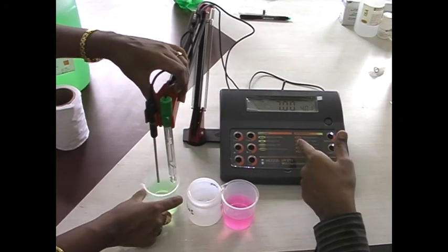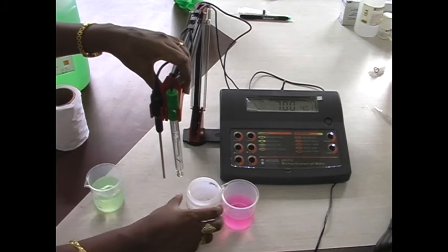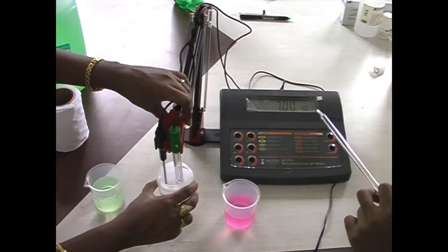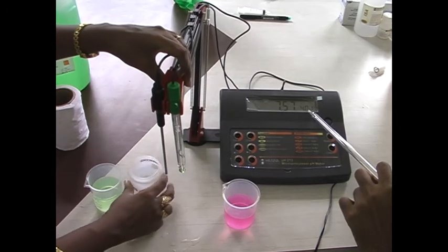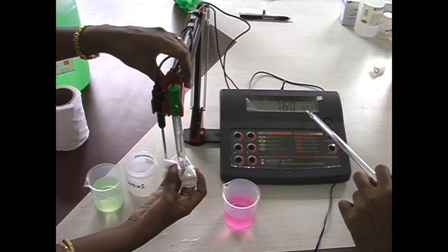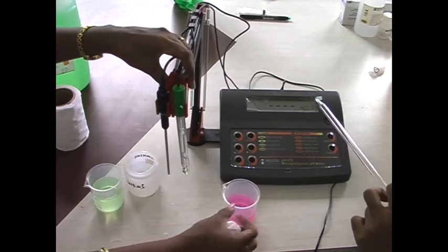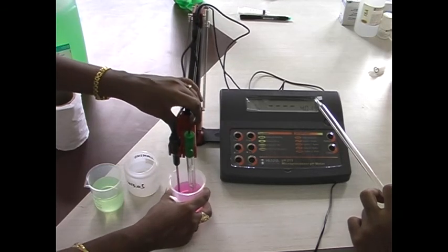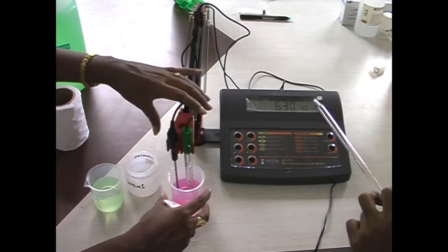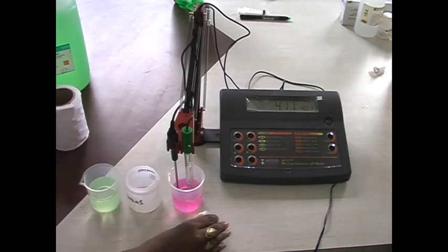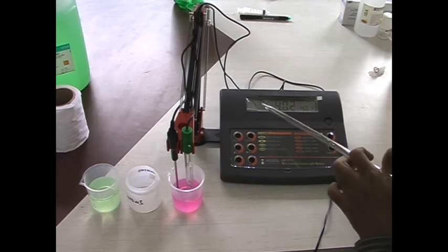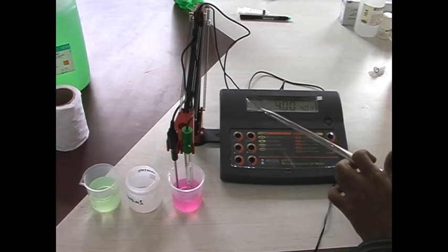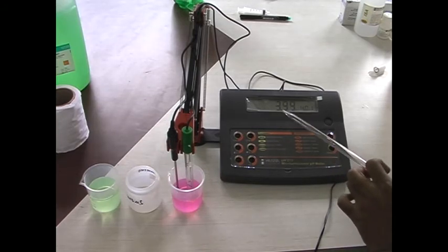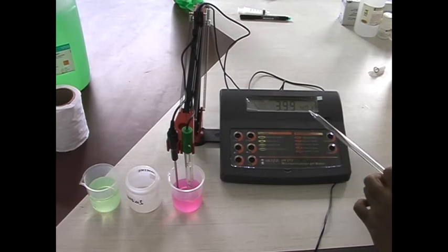So it will store that 7.01 value and it will show the next calibration point on the secondary display, that is 4.01. So just clean your electrode with the distilled water and again place the electrode and temperature probe both in the 4.01 buffer solution. Now again the instrument shows the stability indicator, the hourglass symbol, the actual value, and the calibration point, that is 4.01.